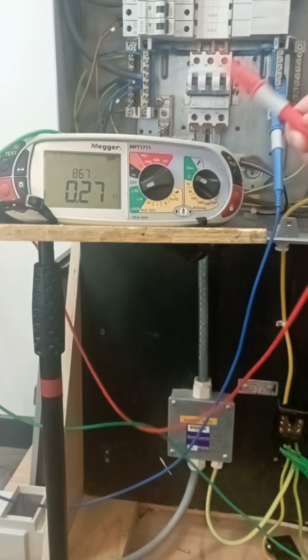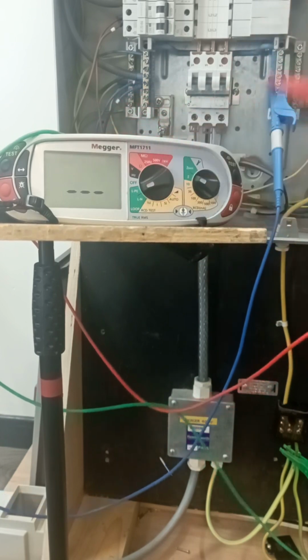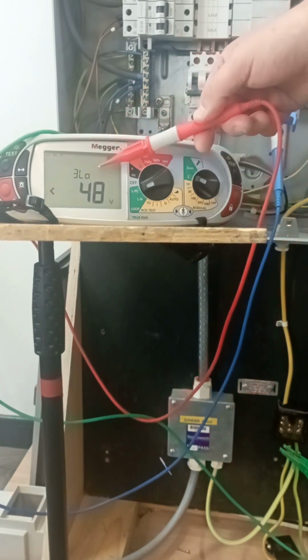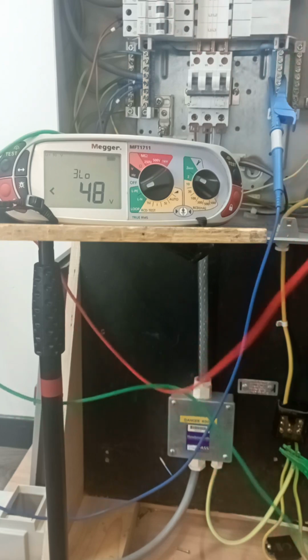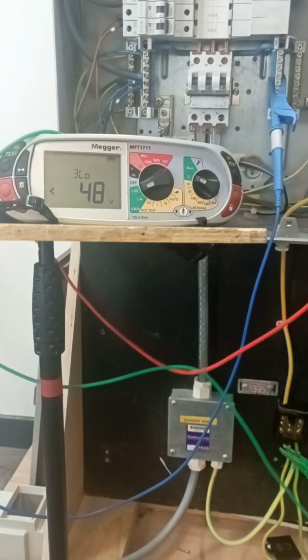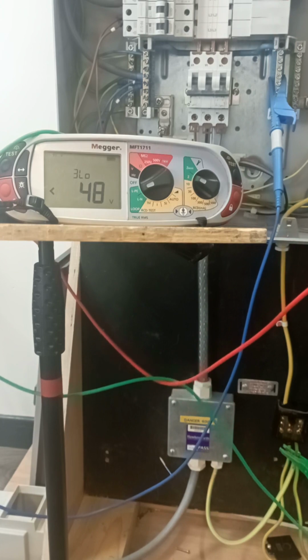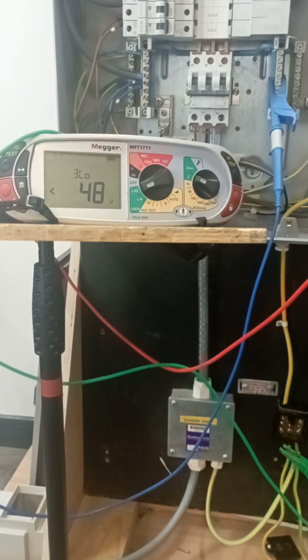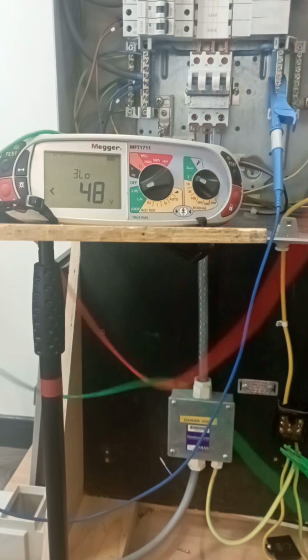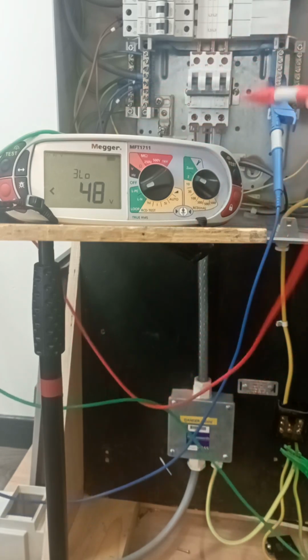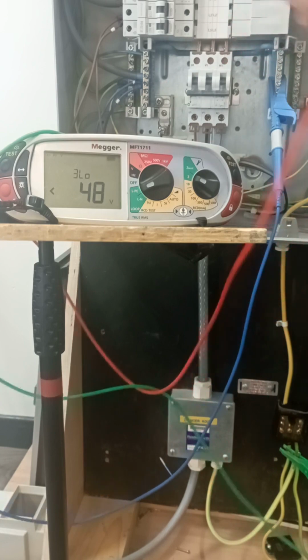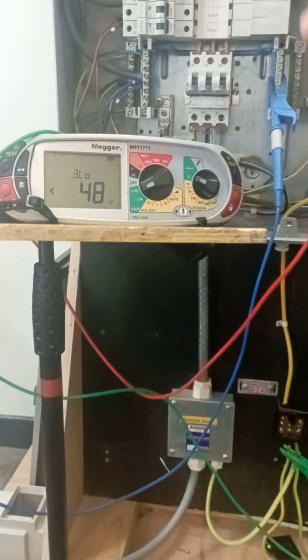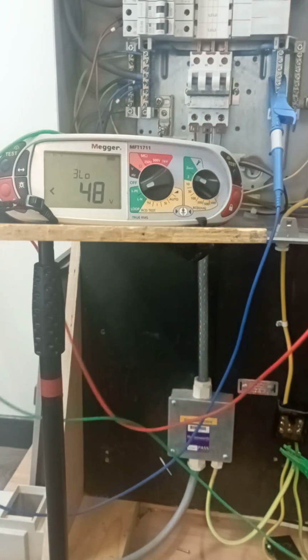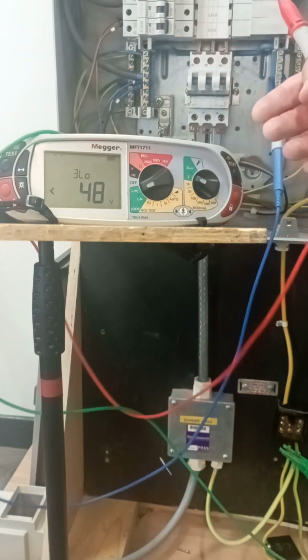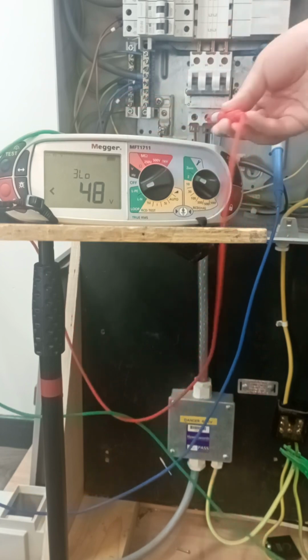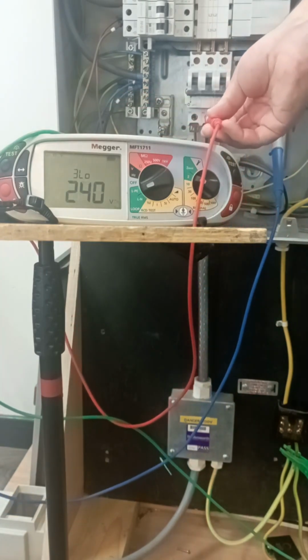Now this meter, you'll see when we turned it on, it went to 3 lead low. The reason we're doing this 3 lead low is because upstream from this board I have a 100 milliamp RCD. So if I did it on a high current test, I would trip out the RCD. Normally, on main incoming supplies, you would be doing it on a high current test unless your risk assessment states otherwise. When we do it in a high current test, we are dumping 18 amps down the earth path. We are stressing that earthing conductor. Normally we would then just carry on with our tests.